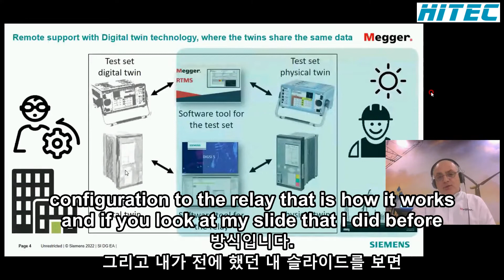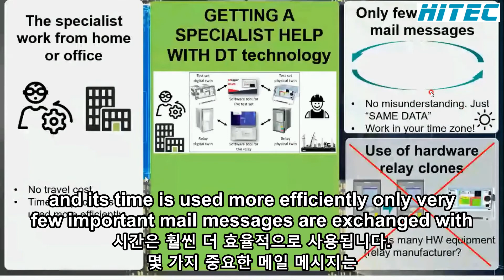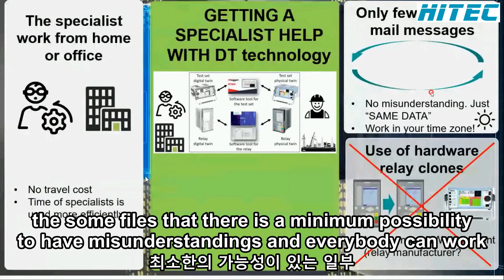Looking at the earlier slide, we don't do it that way anymore - we now pair the specialist with digital twin technology. The specialist can work from home or the office, with no travel cost, and his time is used more efficiently. Only a few important messages are exchanged with files, minimizing misunderstandings, and everybody works in their own time zone. Instead of hardware relay clones, we use software clones called digital twins. This fast support technology is now accessible to any relay specialist, not just relay manufacturers, and we've managed to provide successful help.